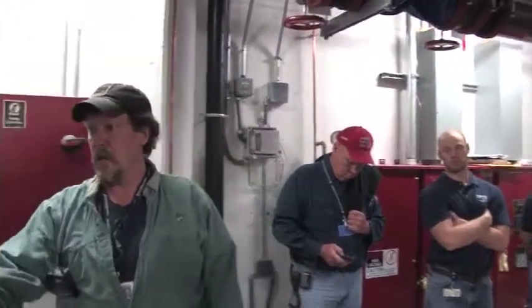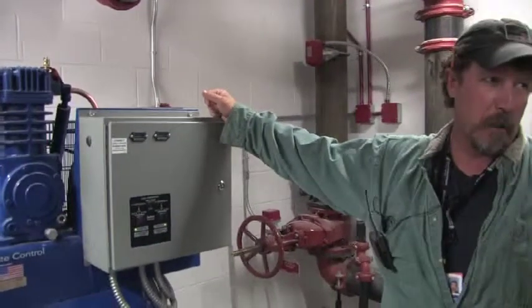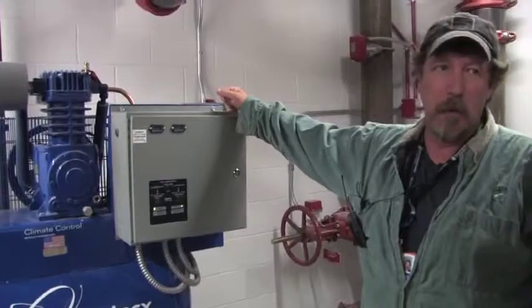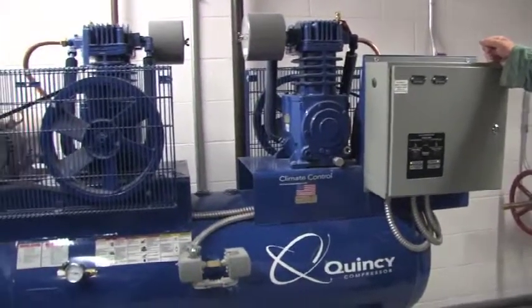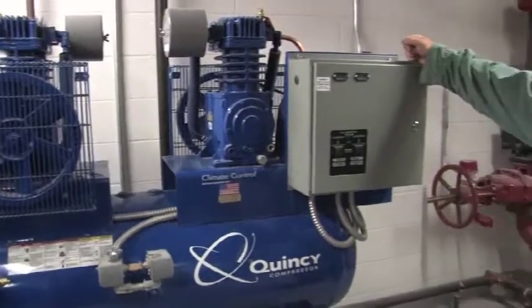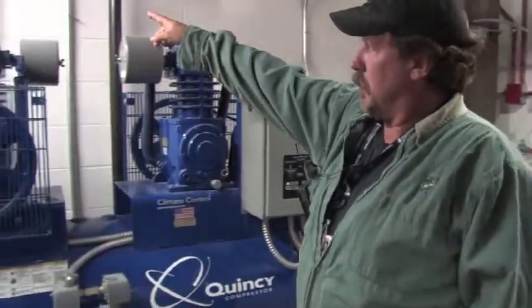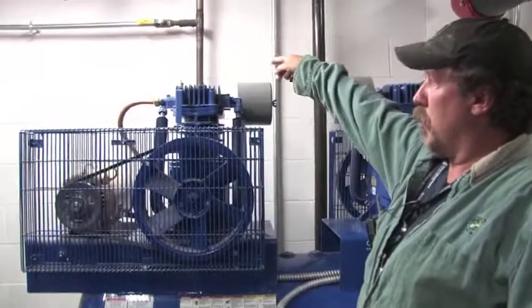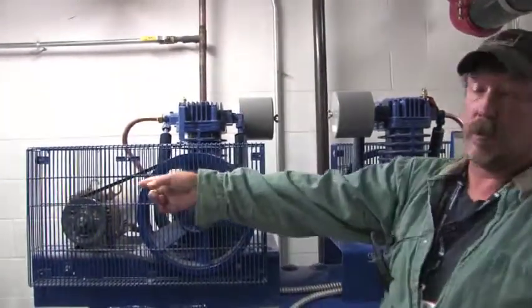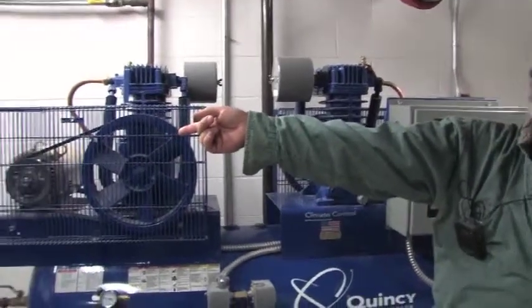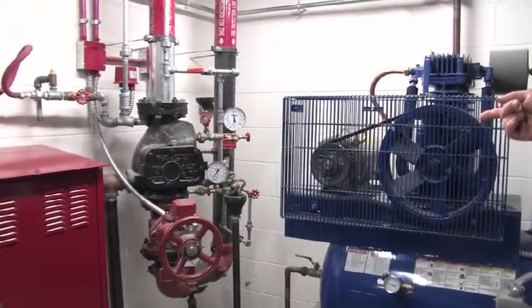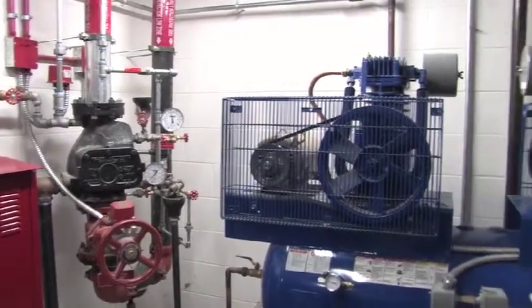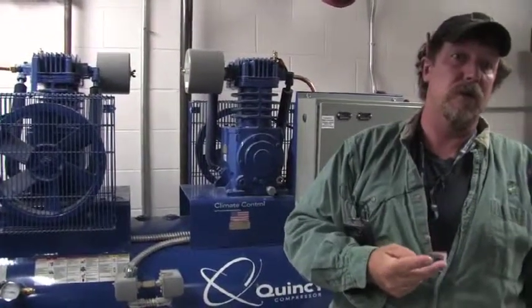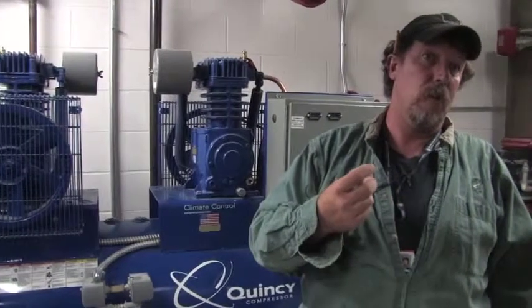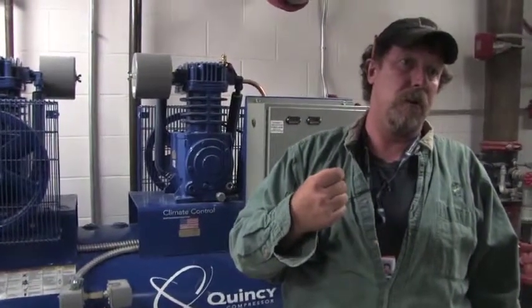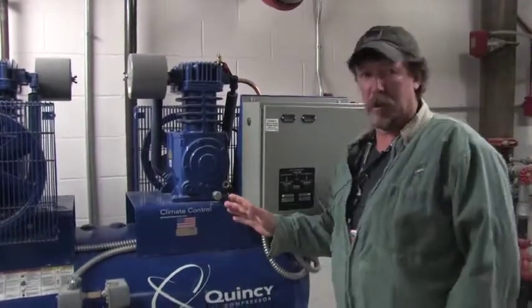Oh, while we're here, this is your air compressor. This baby could probably power up the whole block, but what we're using it for, this gang compressor, is taking care of three things right now. It's piped into this 1.25" copper. It's feeding a dry system, which is doing about 21 sprinkler heads in the ambulance bay. And it also goes up and feeds two other small systems. It feeds the air on the MRI on the second floor and the MRI on the 7th floor. Right now, that's all it's doing.